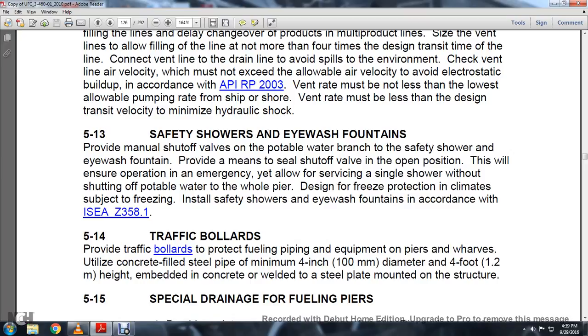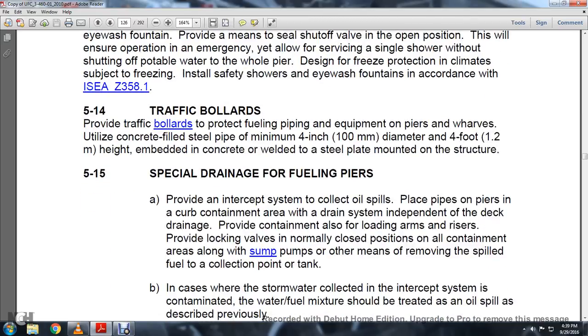Alright, 514 traffic bollards. Provide traffic bollards to protect fuel piping and equipment on the piers. Bollards utilize concrete-filled steel pipe with a minimum 4-inch diameter and 4-foot height, embedded in concrete or welded to a steel plate mounted on the structure.